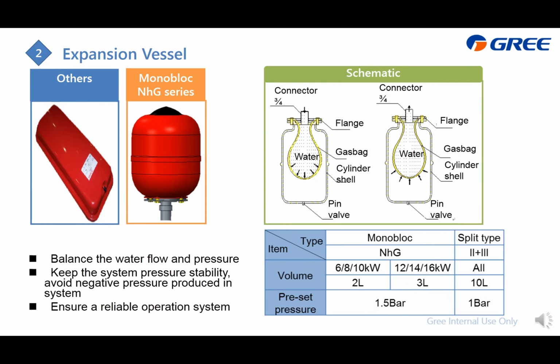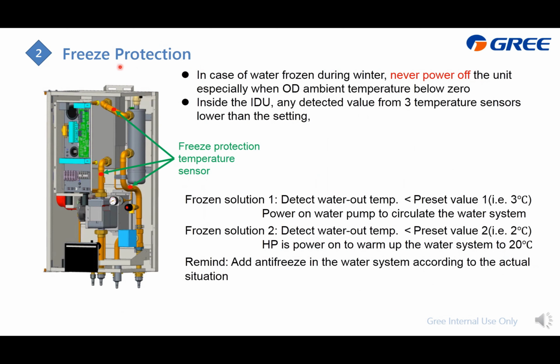Freeze protection. For this one, in low temperature, especially when the outdoor ambient temperature is lower than 0, there is a risk for the water system to become frozen. At that time, it will damage the system, especially for the monoblock, right? And for the system, we recommend that during the cold winter, please never power off, because we have the solution for that. The solution is we will detect the inside water temperature by these 3 temperature sensors, which are located here, here, and here. And solution 1 is if we detect a value less than, for example, 3 degrees, we will turn on the water pump to circulate the water system.